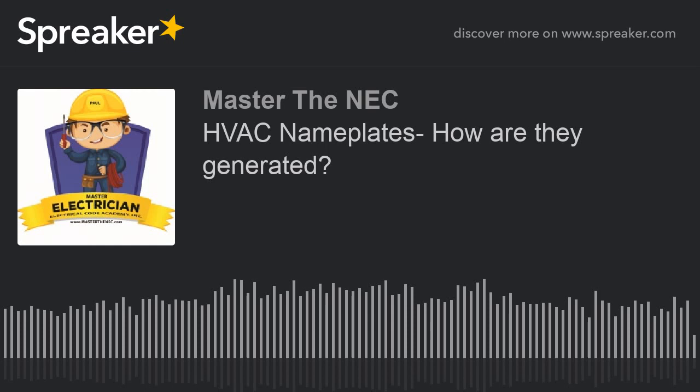Okay, so today's episode, we are going to talk about something that sometimes adds confusion, not just for home inspectors, and we've done a podcast and a video on that, but sometimes electricians also will get confused at the understanding of, I have conductors, and my conductors are rated for 20 amperes, 30 amperes, 15 amperes, and then I have to protect them at that ampere rating based on 240.4. And if it's small conductors like that, 14, 12, 10, then they usually will refer to 240.4(D), which is titled small conductors. And that is true.